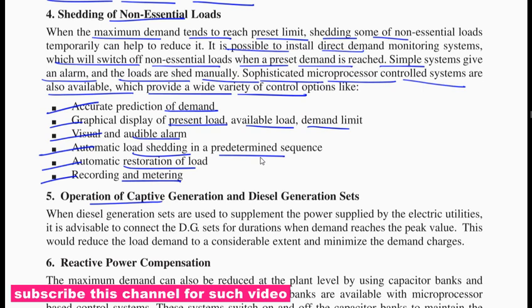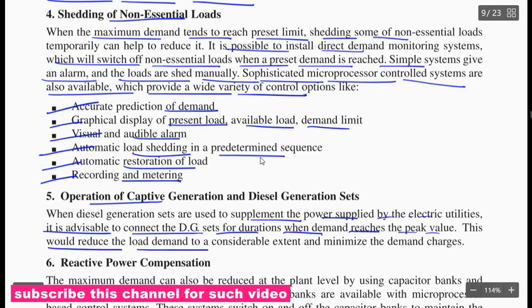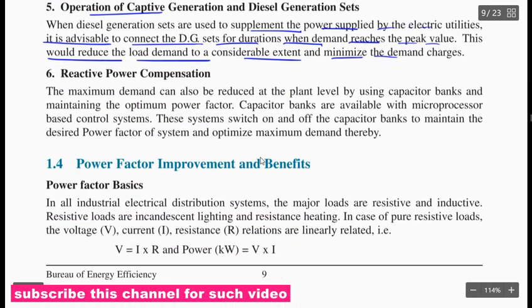When diesel generator sets are used to supplement the power supplied by the electric utilities, it is advisable to connect the DG set for the duration when demand reaches the peak value. This would reduce the load demand to a considerable extent and minimize the demand charge.